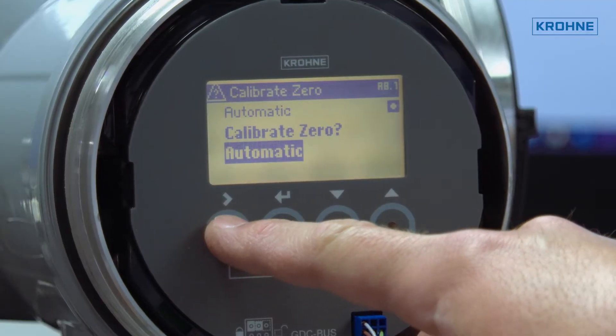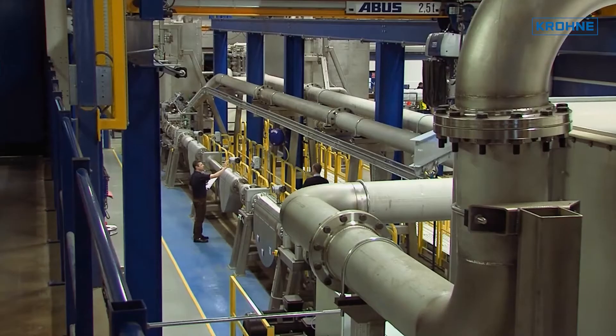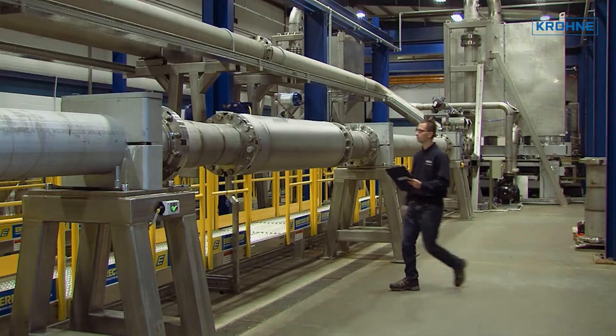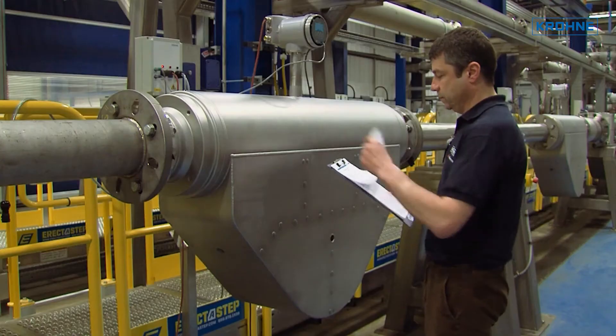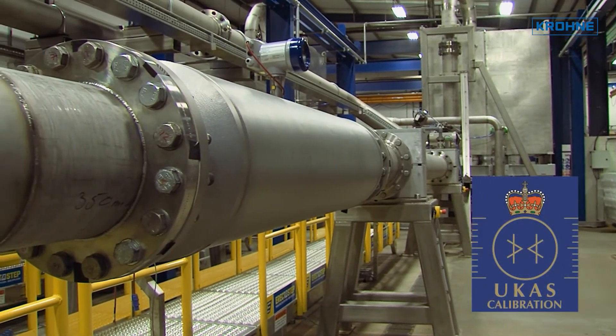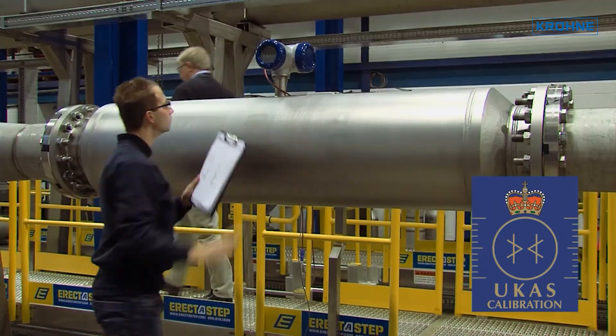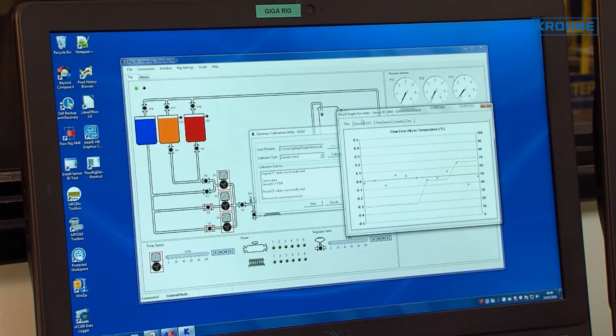There's been significant investment in large line-size calibration rigs, and every new meter undergoes stringent characterisation and calibration tests to guarantee precise and repeatable performance. The Calibration Laboratory is United Kingdom Accreditation Service certified according to ISO 17025, providing complete traceability and quality assurance, and allowing meters to be calibrated up to 0.05% accuracy.